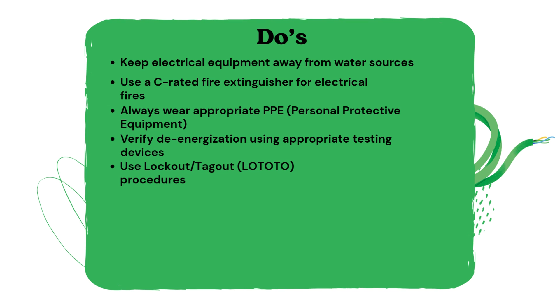Always wear appropriate PPE, personal protective equipment, to ensure you're protected from potential arc flashes or shocks. Verify de-energization using appropriate testing devices — never rely on assumptions, use calibrated devices to confirm circuits are de-energized. Use lockout-tagout (LOTO) procedures to prevent accidental re-energization before starting work. Maintain a safe distance from exposed live conductors, respecting approach boundaries to avoid accidental contact.